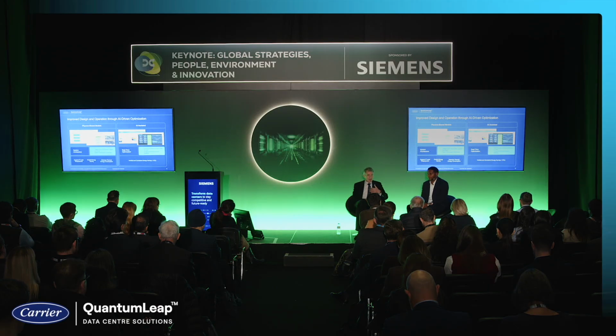In other words, imagine it's a little bit like with cars. You can have different styles of driving. The same thing with a data center. For instance, if you have half load of the data center, so you just need half of your cooling, but you have 100% of your chillers available, you could run all the chillers at 50% load, or half the chillers at 100% load, or 66% at some other load. So there's an array of solutions.